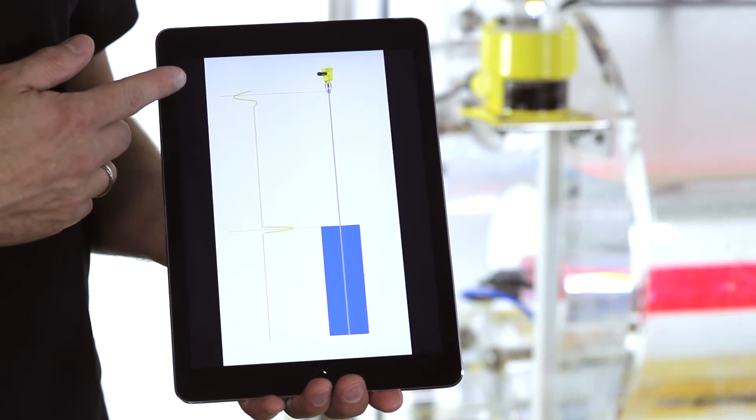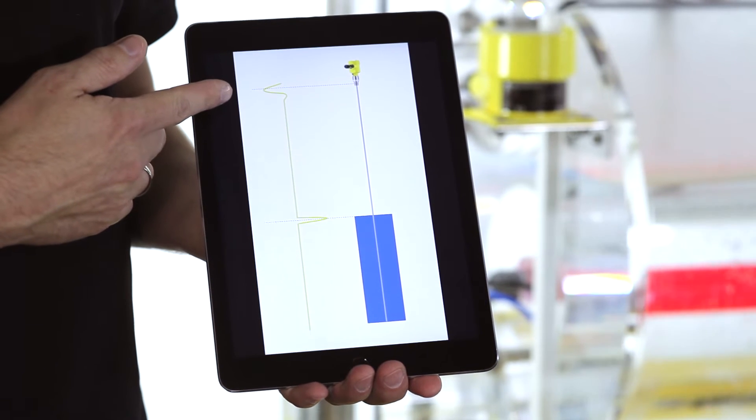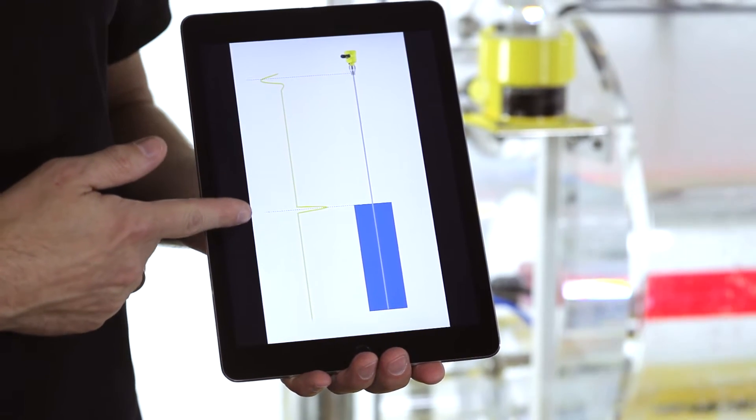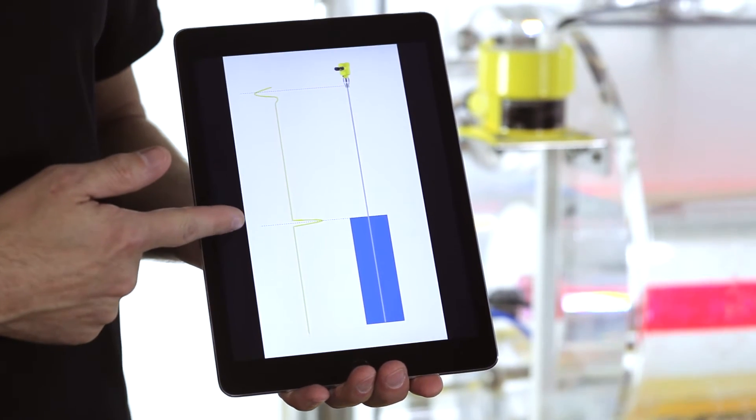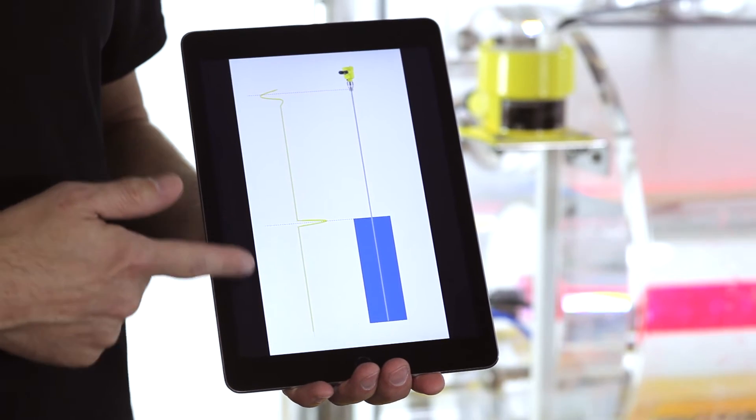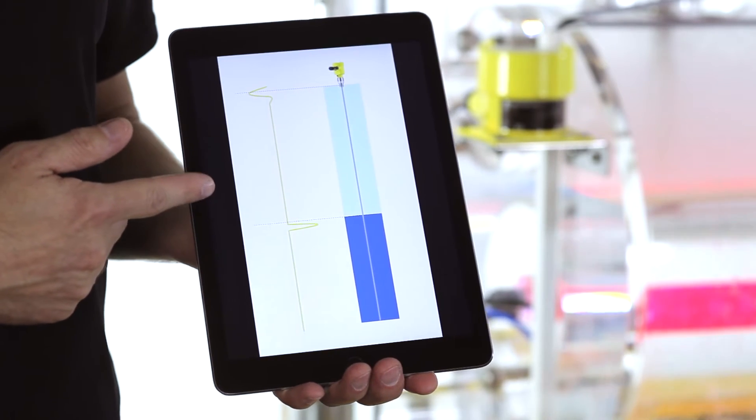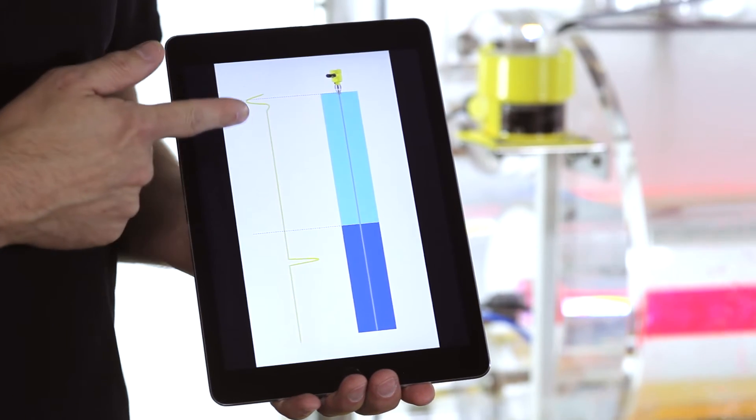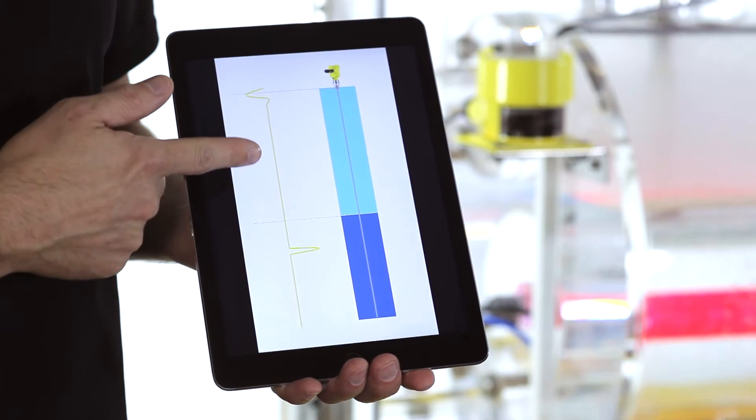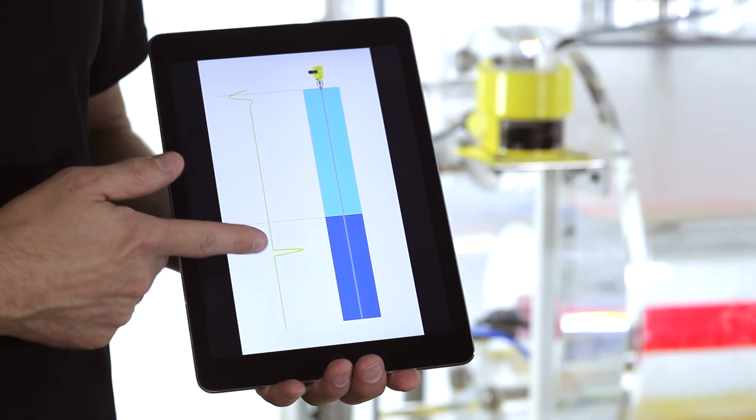Guided wave radar instruments generate high frequency energy which is reflected by the medium for level measurement. In steam boilers, however, the steam is influencing this high frequency energy so that there is a measurement deviation.